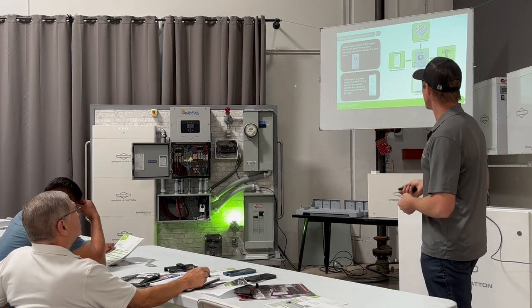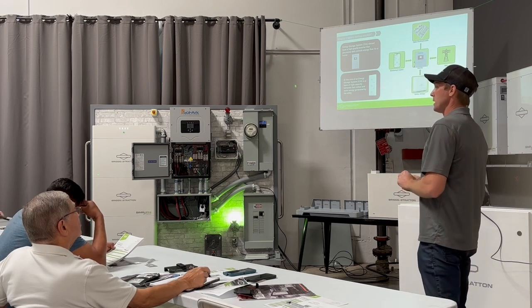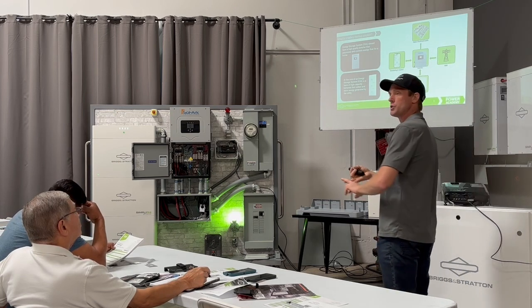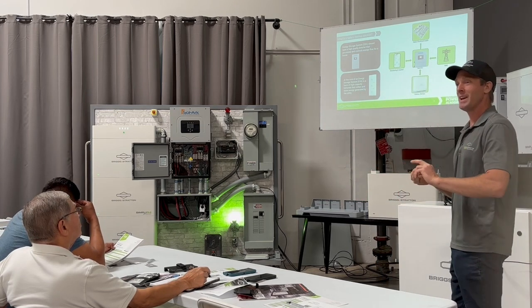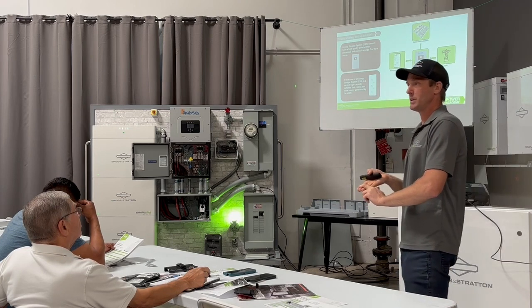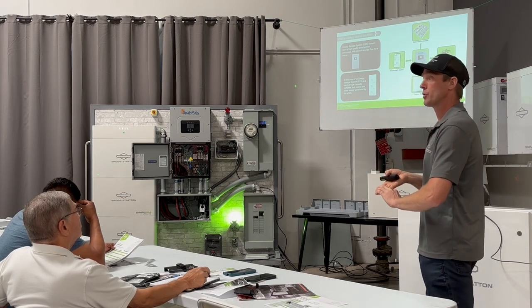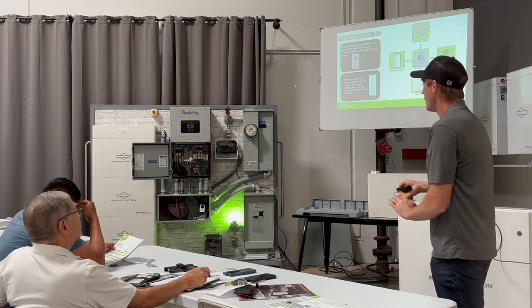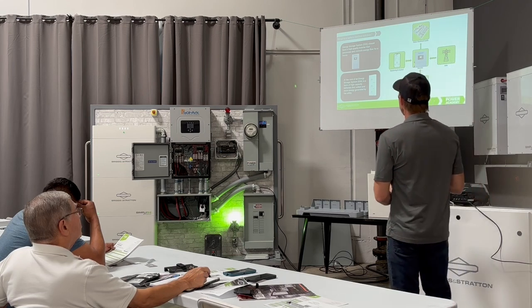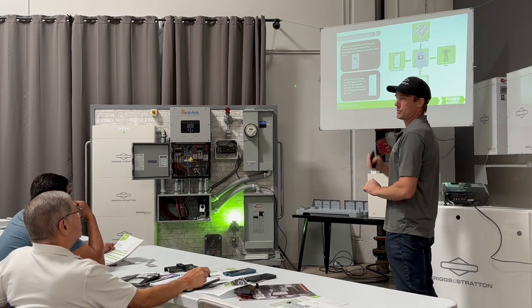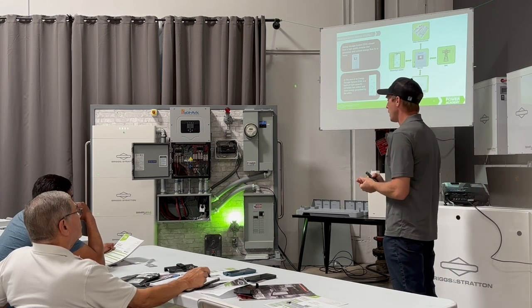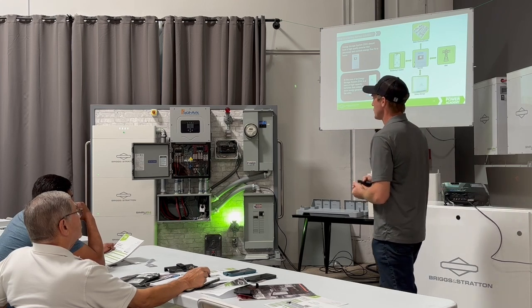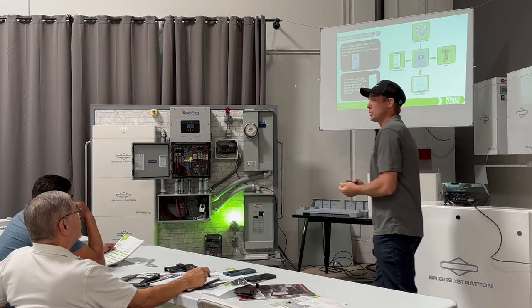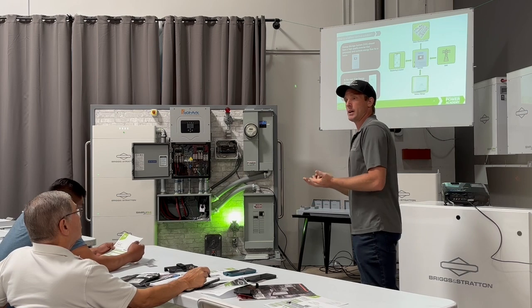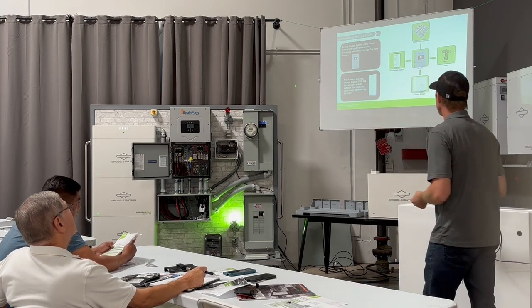So the Sol-Ark inverter can do that. It can take in solar, utility power, generator power, AC coupled solar, meaning microinverters or string inverters bringing power through the Sol-Ark. So there's a lot of flexibility with this inverter. It has rapid shutdown capability built in so you can use different brand rapid shutdowns, and we can talk about those.